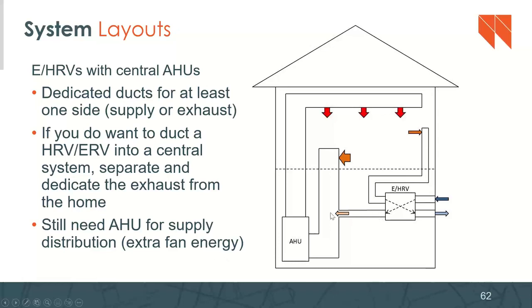So in other words, your fresh outside air is coming in. This was the example that I said earlier. This is it to a T. This was that actual example. When the air handler is not running, the return side of your heating and cooling ductwork is extremely well ventilated. This outside air is just going to follow the path of least resistance, usually falling out the return side of your system, or it's going to be piped into your air handler and just sit there. It's going to leak out through the air handler and into your mechanical closet or something, right? More often we see it going out the return side. But that's not distributing it to the house. It's not distributing it where it needs to go. It will only distribute it when the air handler is actually running.